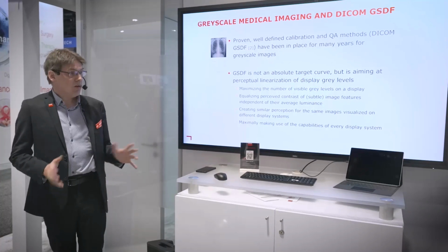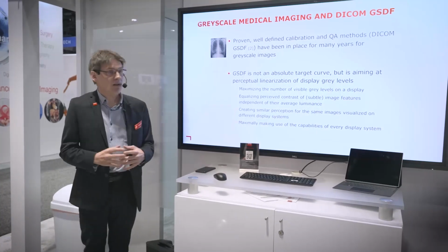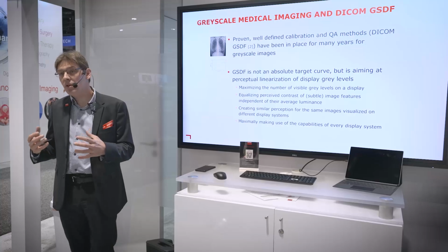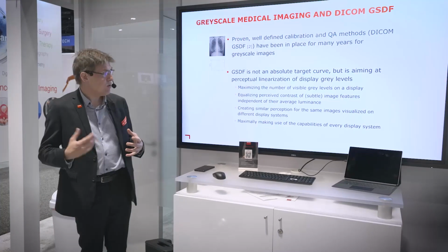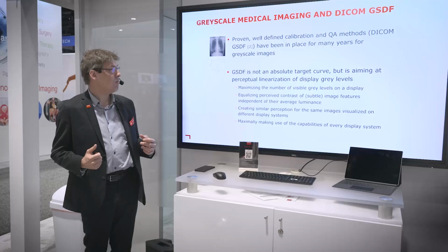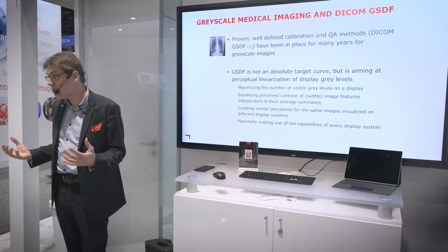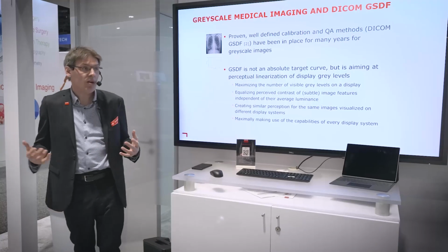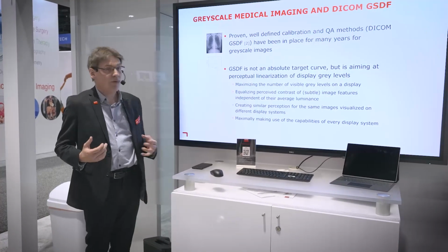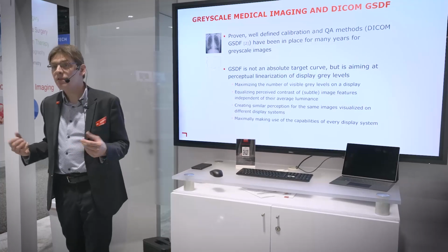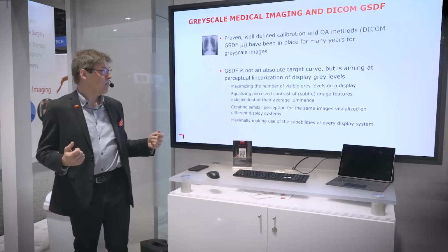Let me take you a step back to very briefly explain how grayscale calibration is done, because we will need that to explain how we solve the color calibration problem. So DICOM GSDF has been used already for a very long time. It's an industry standard. It's also in regulations worldwide. So in fact, every medical display is being calibrated to DICOM GSDF.